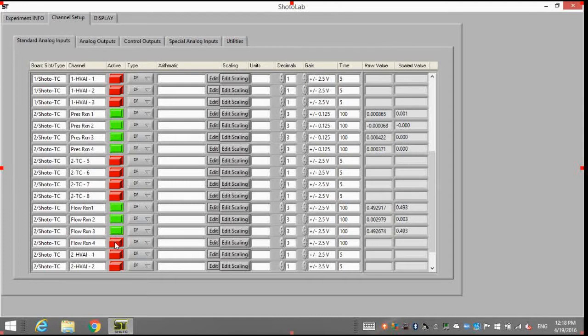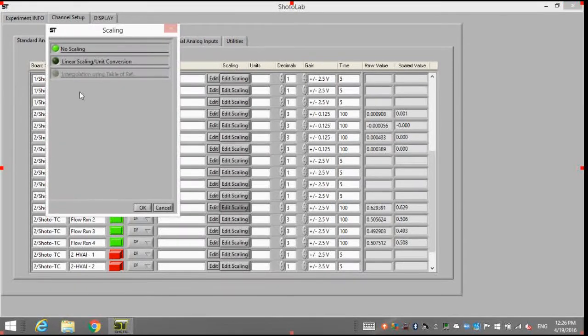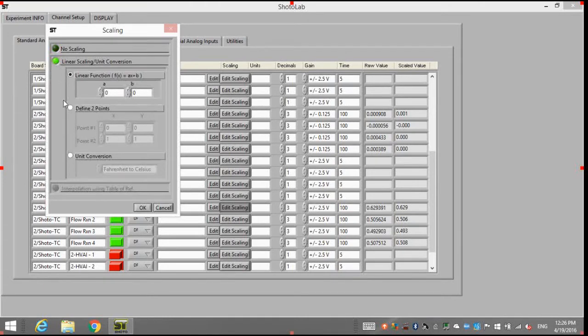As you can see, the second reading isn't reading correctly. Let me take a look at it real quick. The connector was loose, and that fixed the problem. As with the pressure transducers, the flow meters need to be calibrated, and let's do that real quick. The spec sheet says that these flow meters read 0.5 volts at 0 flow and 2.5 at 100 cc.